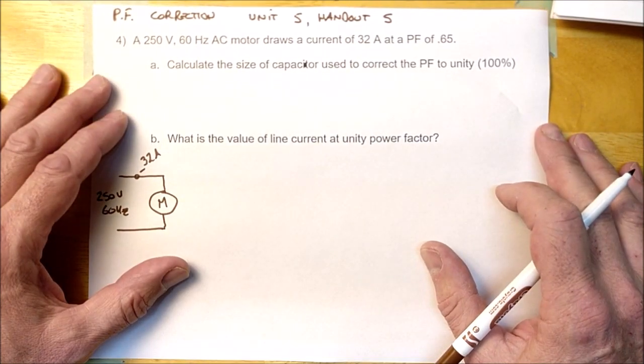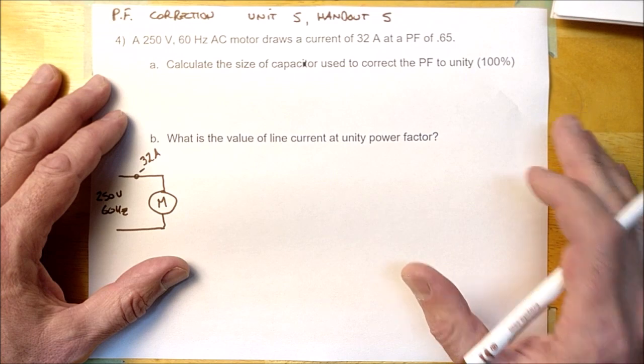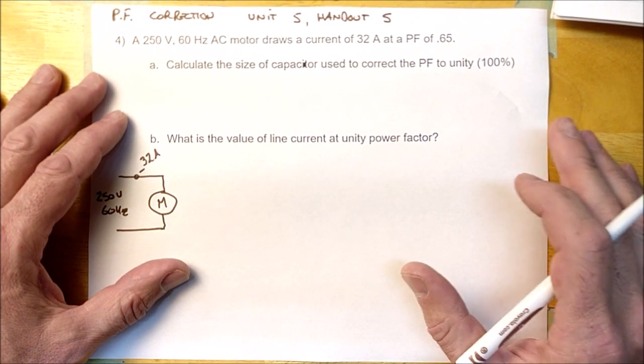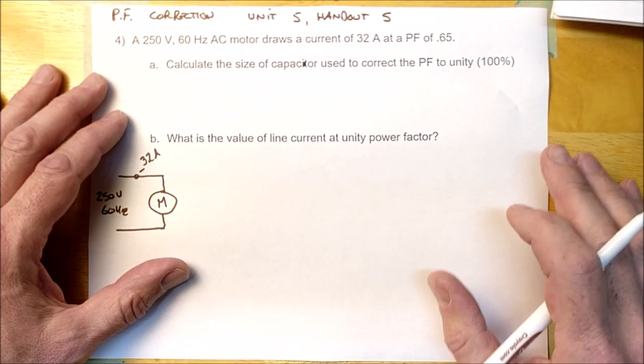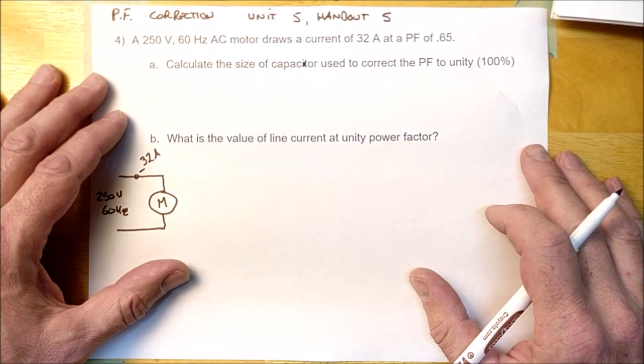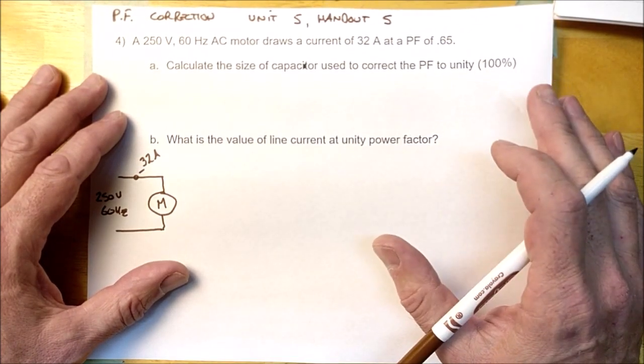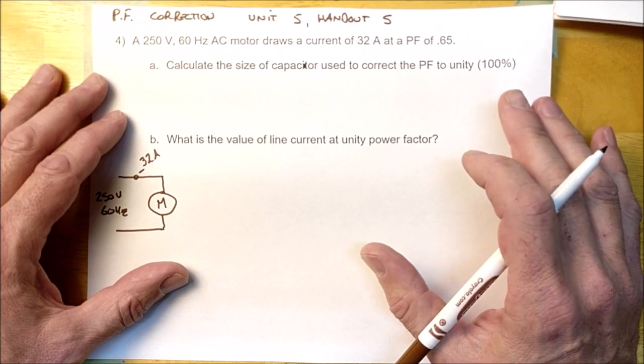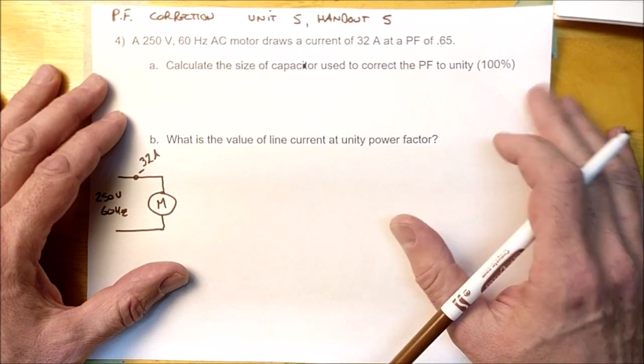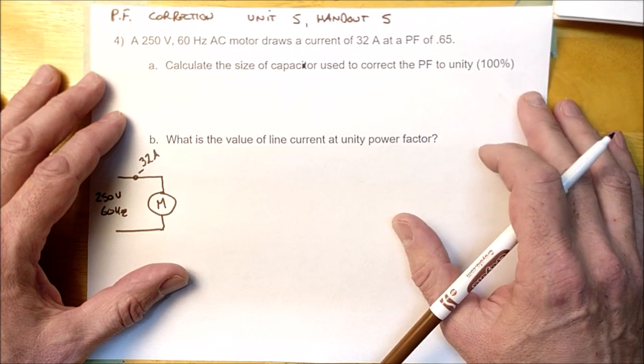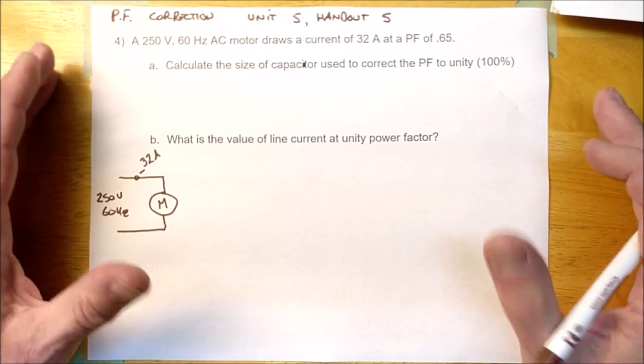They've got to supply all that current that nobody's paying for, and that annoys them. So what they do is they continue to charge those customers for the true power only, but they also monitor the customer's power factor. And if the power factor is worse than 90% or 0.9, they actually tack on an additional charge — a penalty for having a poor power factor. The extra charge is sufficiently high that it would encourage that customer to add capacitors to improve the power factor to at least 90%.